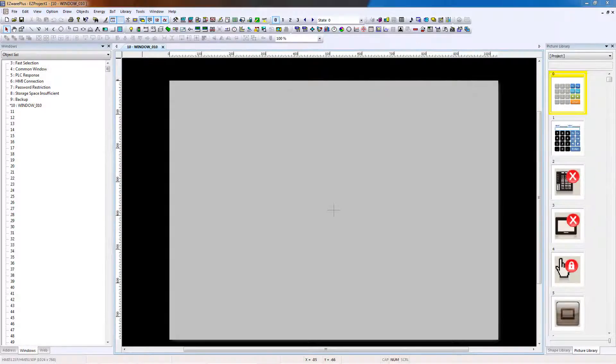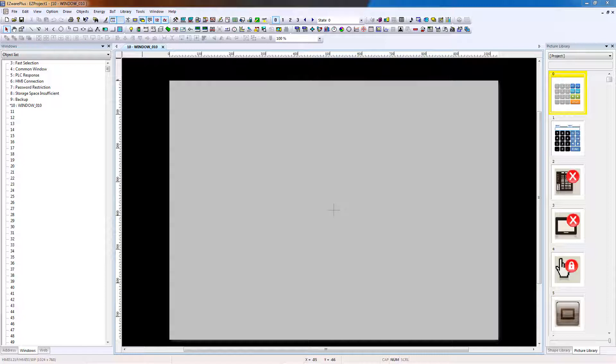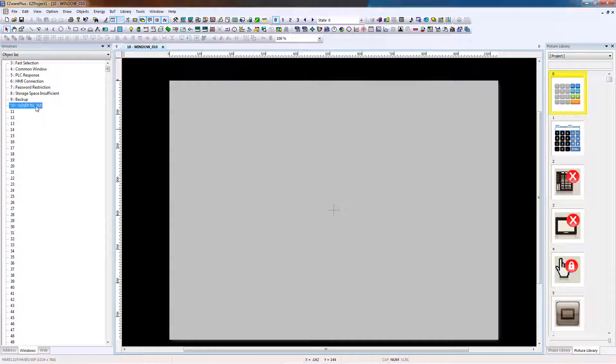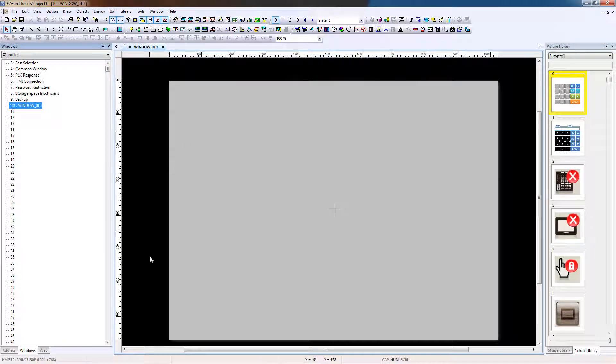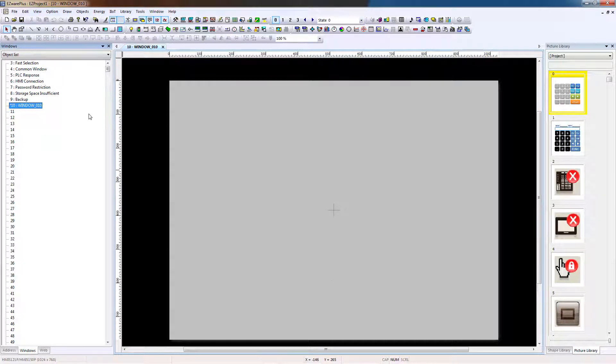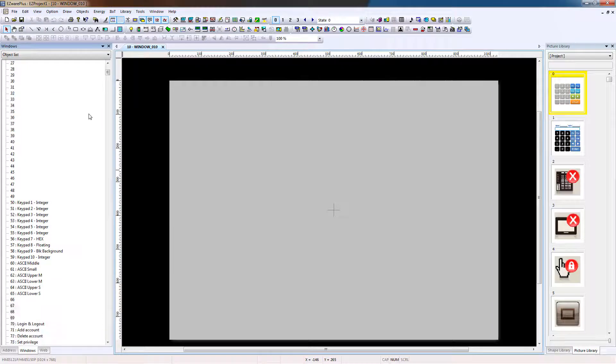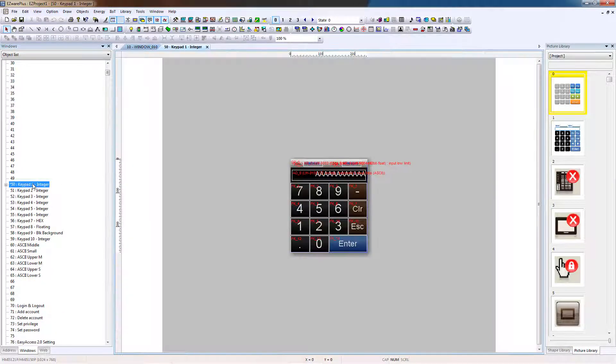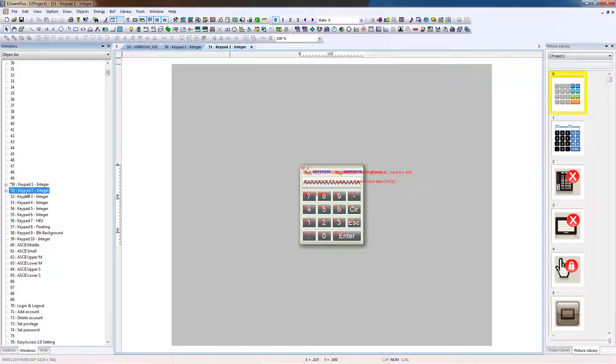EZwarePlus uses the term window to refer to the screens that can be displayed or programmed in the HMI. By default, EZwarePlus uses Window 10 as the startup window that is displayed whenever the HMI powers up or reboots. When a project is created with a template file, it starts with the default Window 10 and a number of windows for specialty functions such as keyboards and error messages. The Quick Start project will use five windows.